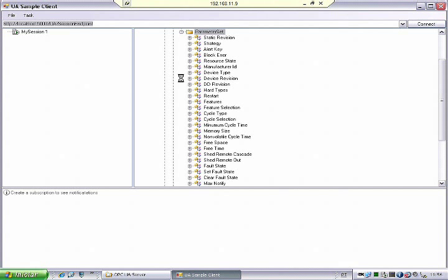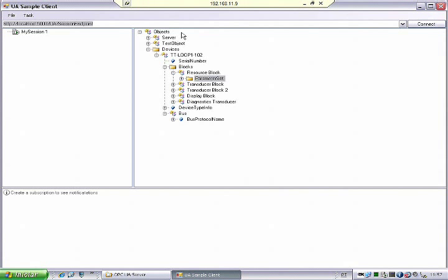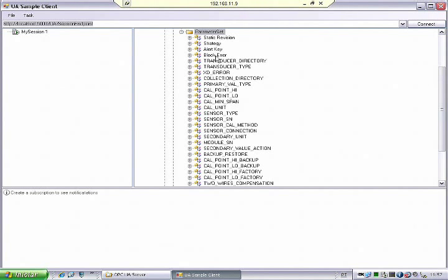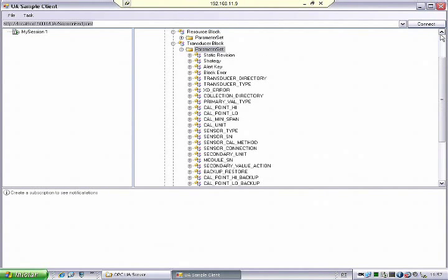The EDD server — the second component added to the server — is able to give me all the parameters. It becomes interesting because it provides the data type for each parameter: whether it is enumerated, a string, a datetime, or something else. Here we have the transducer block. You don't need to know what a transducer block is in Foundation Fieldbus — this is a parameter, and the information model says to create a variable to hold the parameter value.